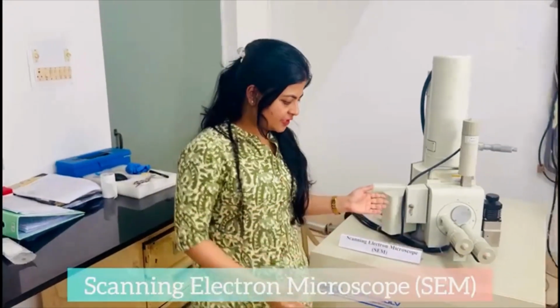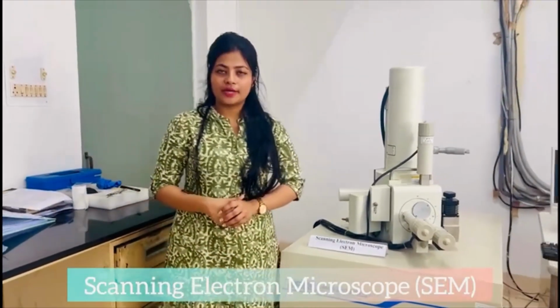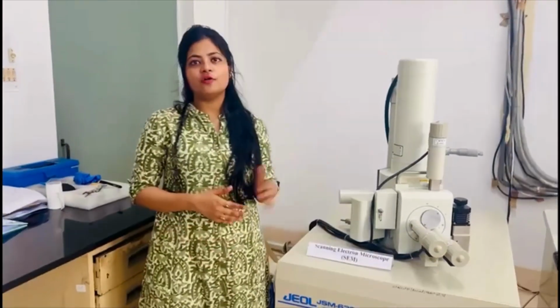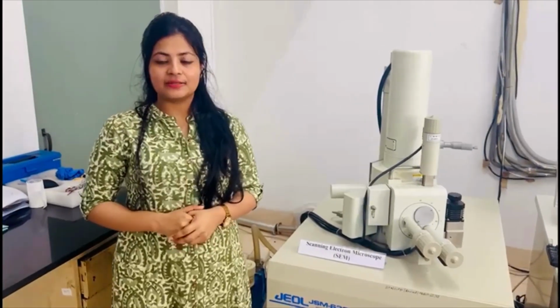So this machine in front of you is known as the Scanning Electron Microscope, also called SEM. The make of this instrument is Jeol, Japan. The model is JSM 6390LV. A few specifications of this instrument are a resolution of 3 nanometers in high vacuum mode and 4 nanometers in low vacuum mode, and 30 kV accelerating voltage. The magnification of this instrument can go from 5 to 3 lakh times. The image modes present here are secondary electrons and backscattered images.